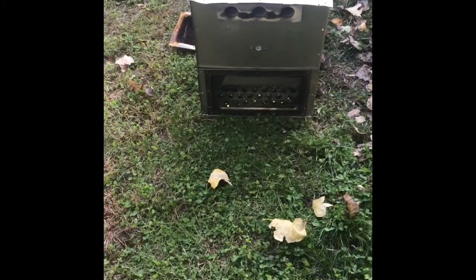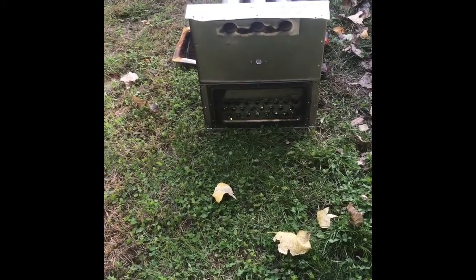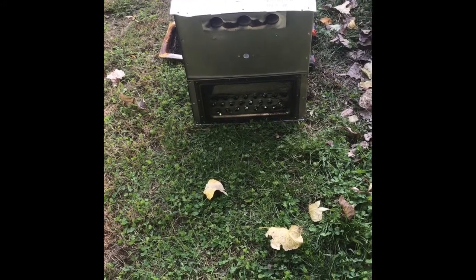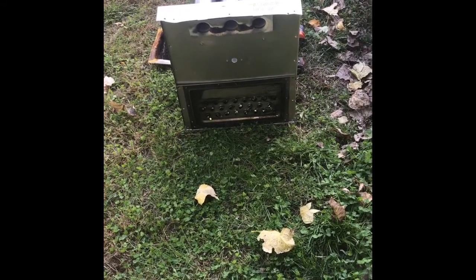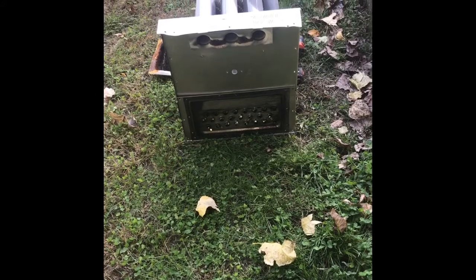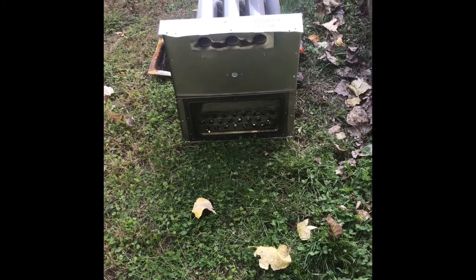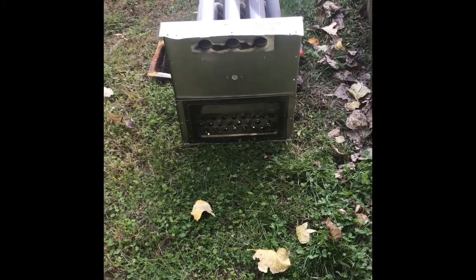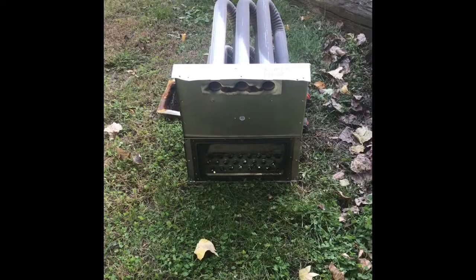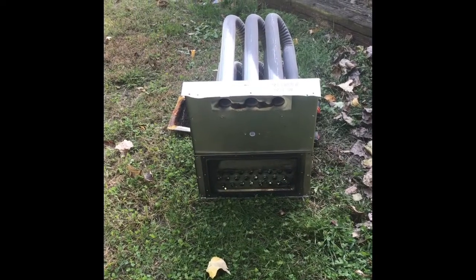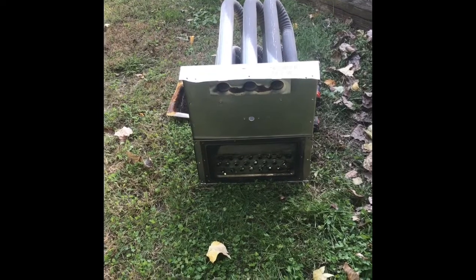That being said, this shows the importance of setting up your combustion properly. This shows the importance of doing a combustion analysis. If I had not tested the carbon monoxide level, I likely would not have diagnosed it as a bad heat exchanger.